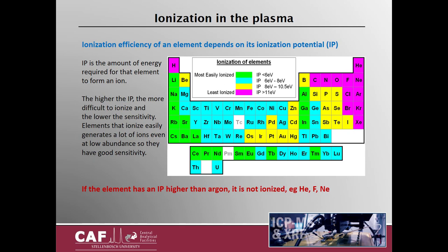The ionization efficiency of an element depends on its ionization potential — the amount of energy required for that element to form an ion. The higher the ionization potential, the more difficult it is to ionize and the lower the sensitivity. Elements that ionize easily generate a lot of ions even at low abundance, so they will have very good sensitivity. If the element has an ionization potential higher than argon, it is not ionized in the argon plasma — for example, helium, fluorine, and neon.